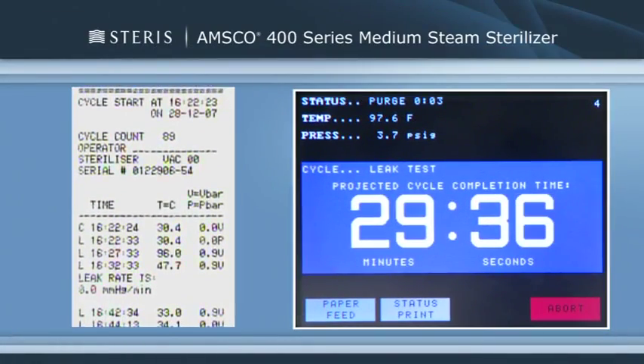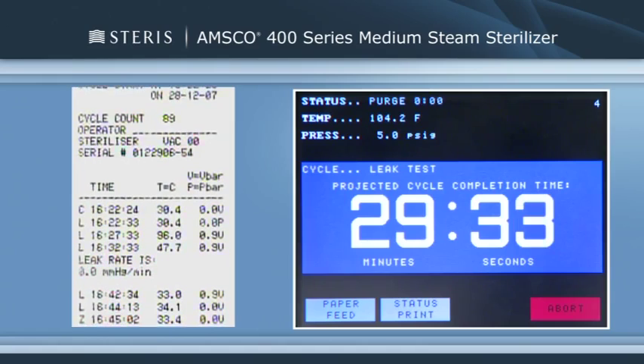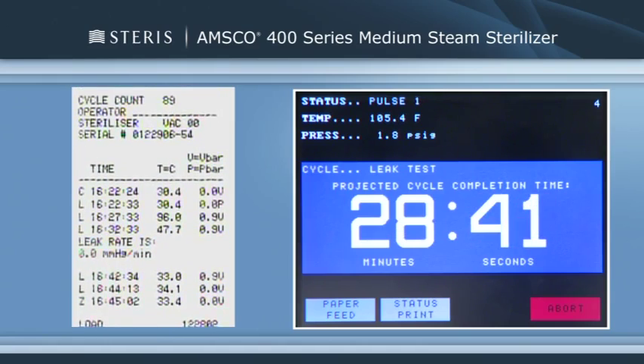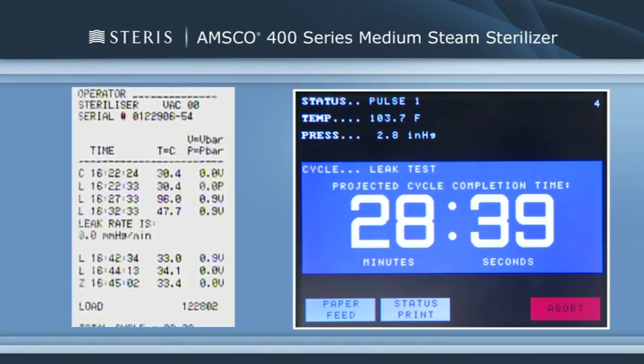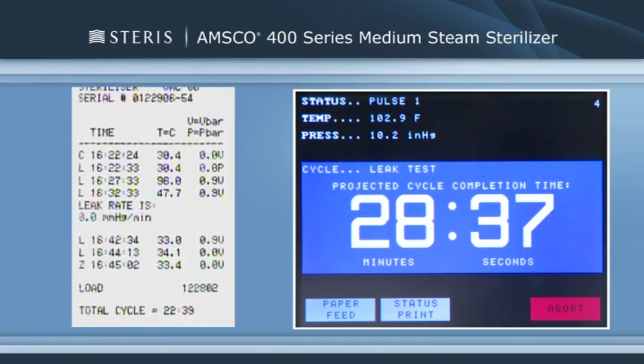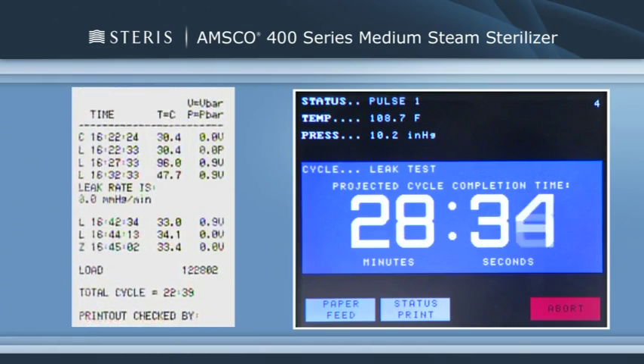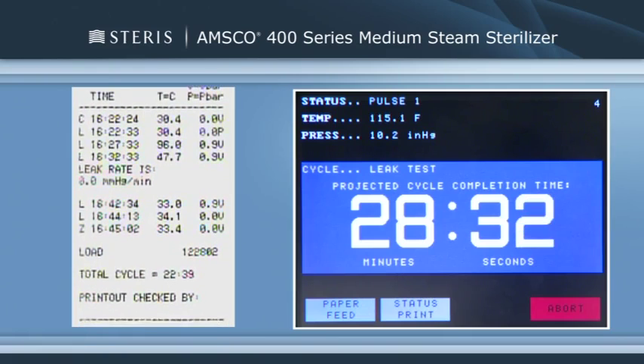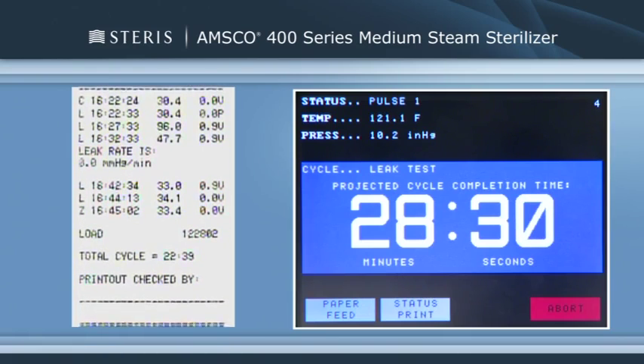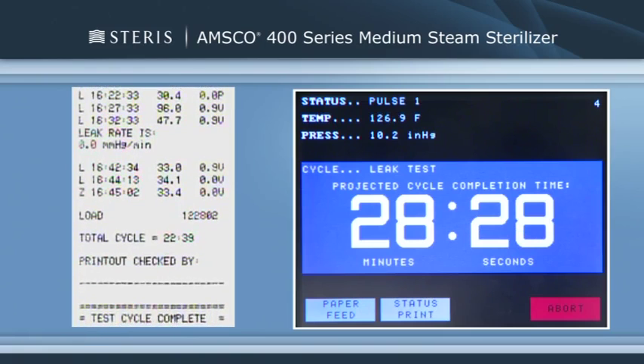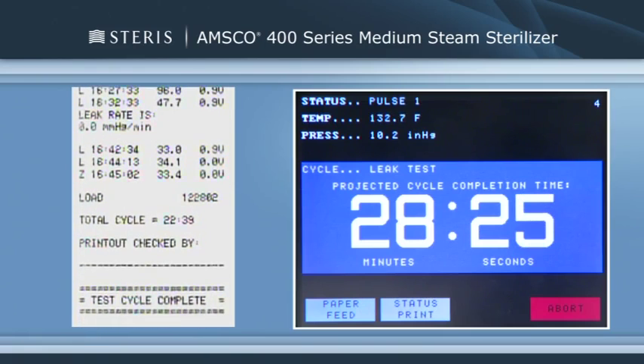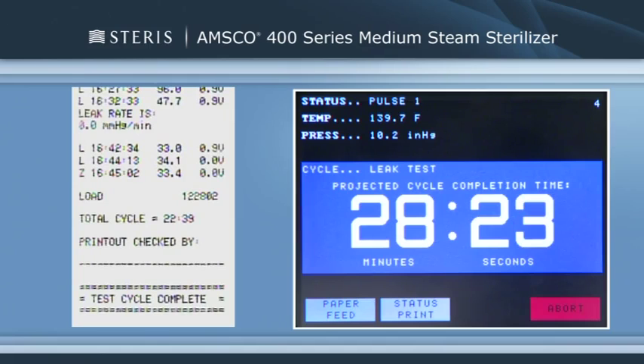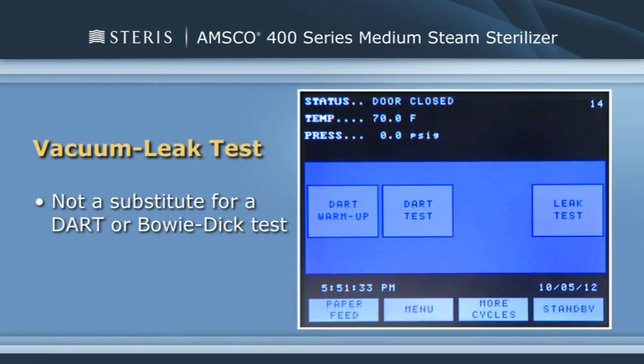The entire vacuum leak test cycle is also documented on the printout and includes a leak rate value. A leak rate of less than 1.0 millimeters of mercury per minute is considered acceptable. Leaks greater than this need to be addressed by service or maintenance personnel who can monitor the airtightness of the system and make repairs or adjustments as needed. Only gravity cycles should be run if the leak rate is greater than 1.0 millimeters of mercury. It is important to note that the vacuum leak test is not a substitute for a DART or a Bowie-Dick test.